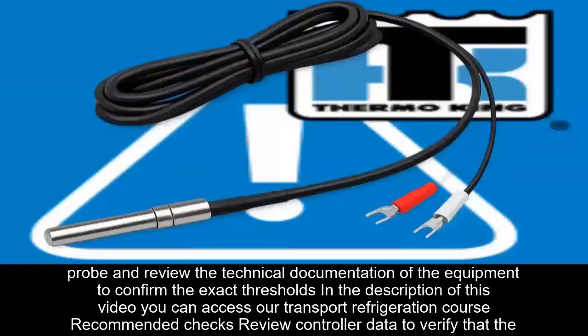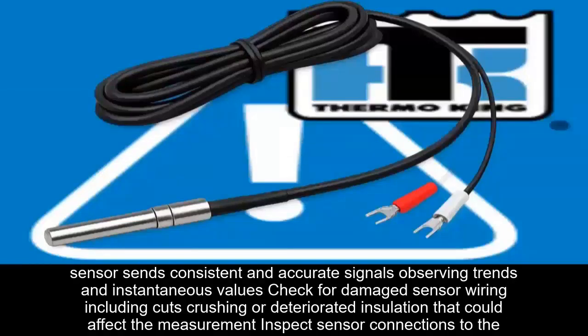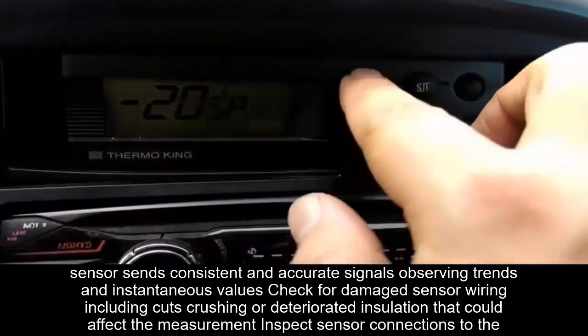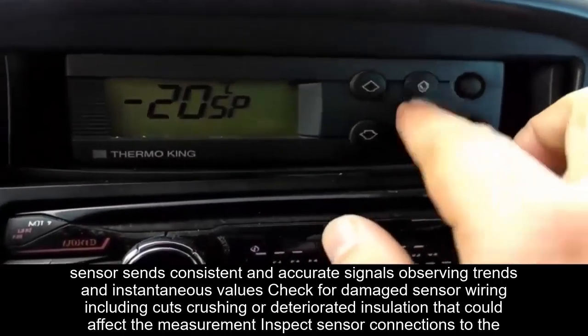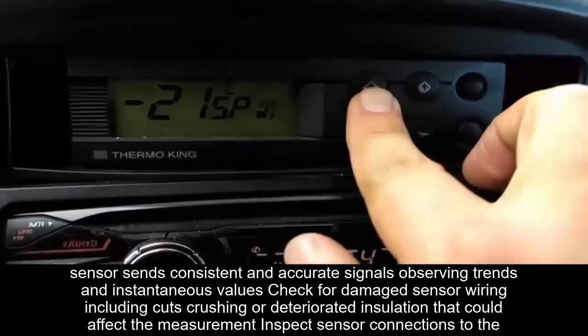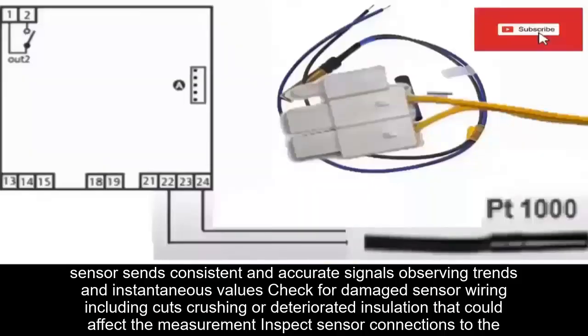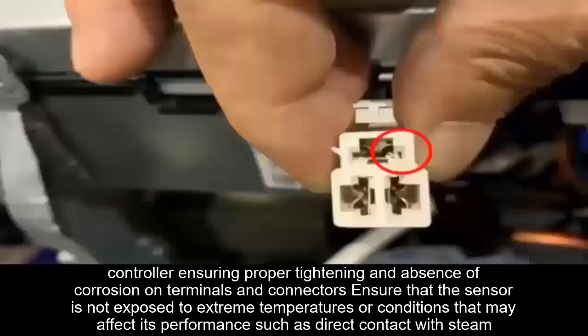Recommended checks. Review controller data to verify that the sensor sends consistent and accurate signals, observing trends and instantaneous values. Check for damaged sensor wiring, including cuts, crushing, or deteriorated insulation that could affect the measurement. Inspect sensor connections to the controller, ensuring proper tightening and absence of corrosion on terminals and connectors.